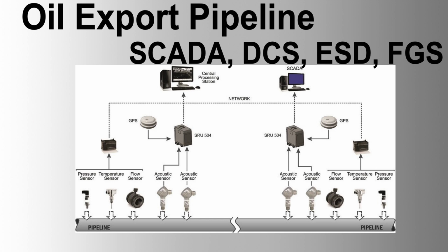Control Center and Handover Philosophy. Master Control Room, MCR, located at primary pumping station, monitors overall pipeline operations. Backup Control: Fujairah AMCR as backup, Swayhan IPS for local station control. Handover Protocol: point of control and handover rules for switching command power between devices and ICSS using request-accept and offer-accept protocols. Fallback Strategy: automatic fallback to backup links and control centers in case of communication failures. This comprehensive control system philosophy ensures safe, efficient, and reliable operation of the 500-kilometer oil export pipeline, integrating advanced control, monitoring, and safety systems.